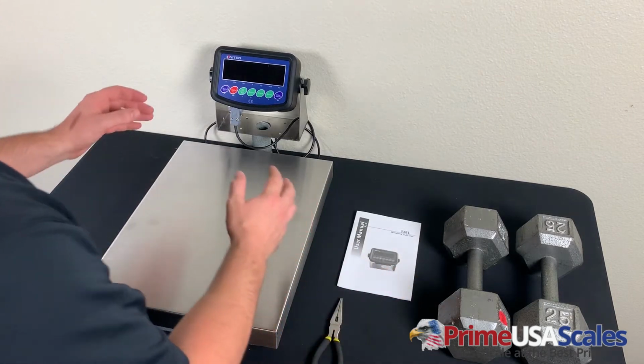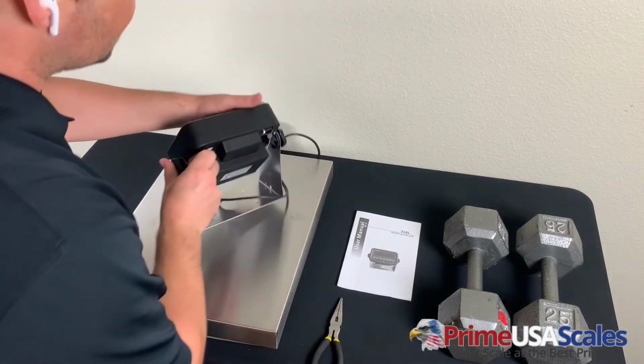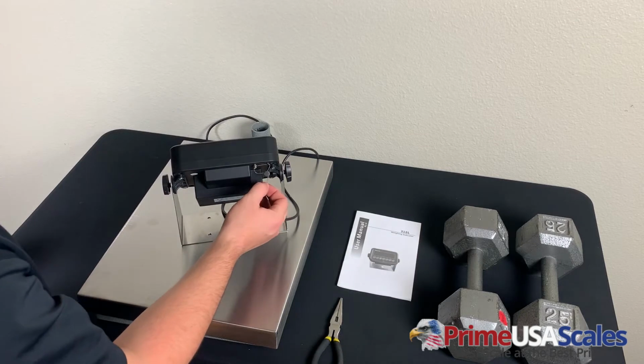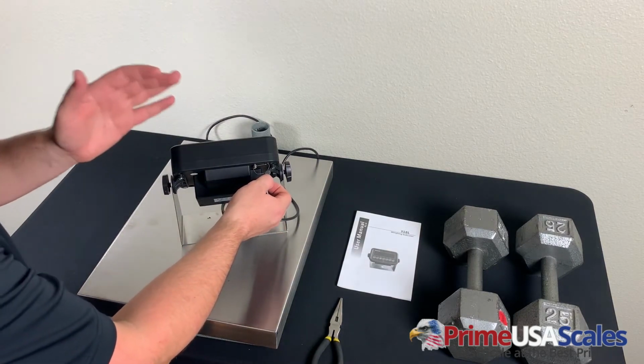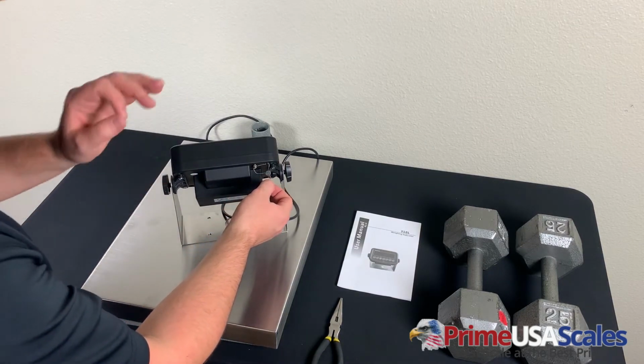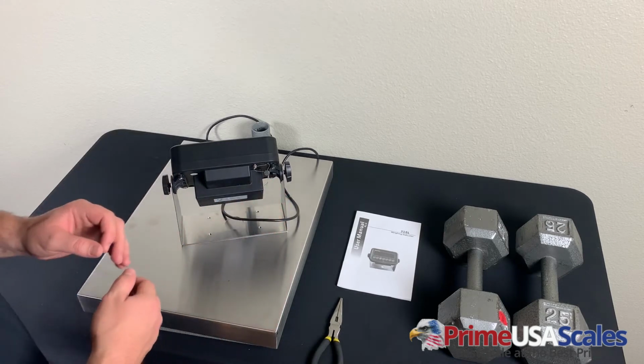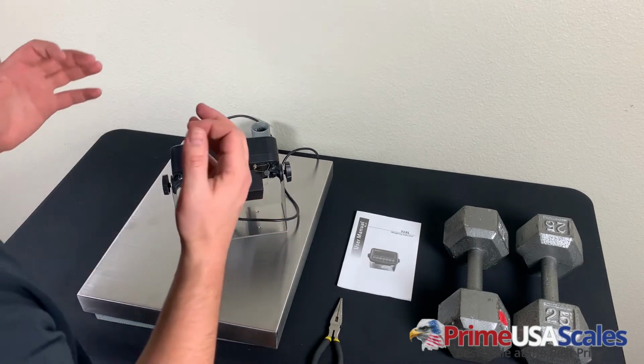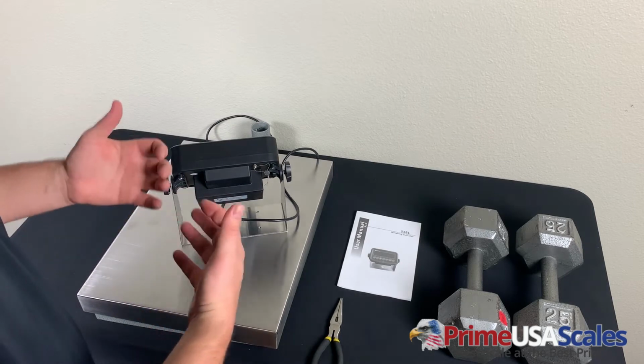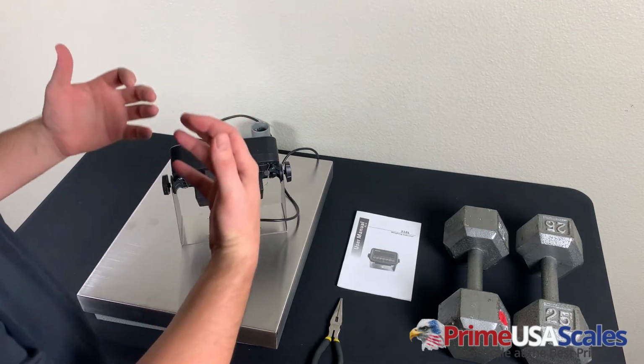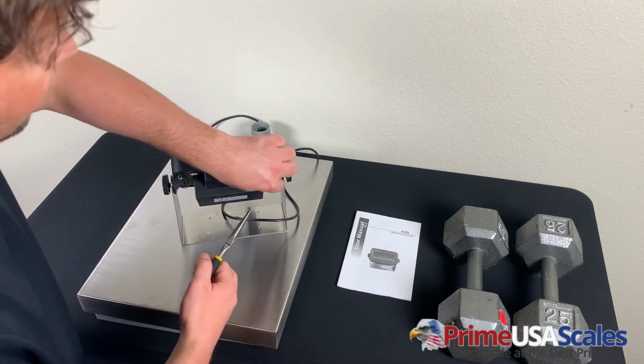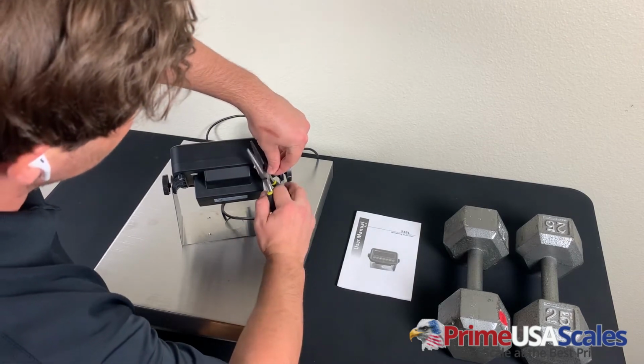Now the way that we ship our indicator is that you need to break a seal on the back here in order to get to the actual calibration procedure. This is put into place to avoid customers from making the mistake of uncalibrating the indicator once it arrives, since we ship the product calibrated to our customers. So to start off, we first want to go through and break this seal.